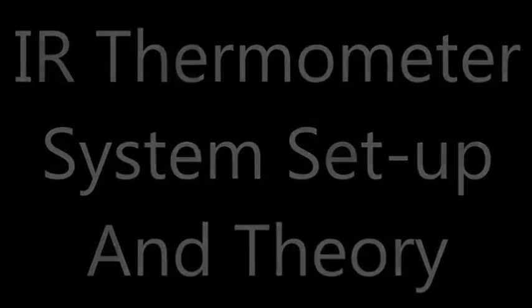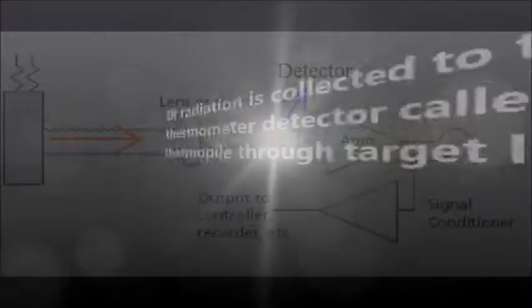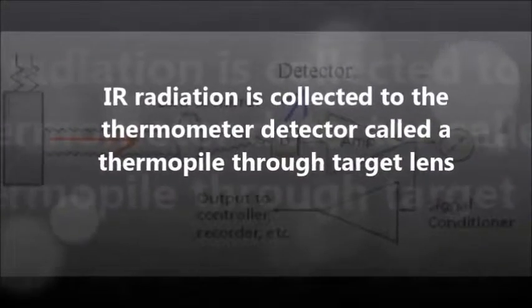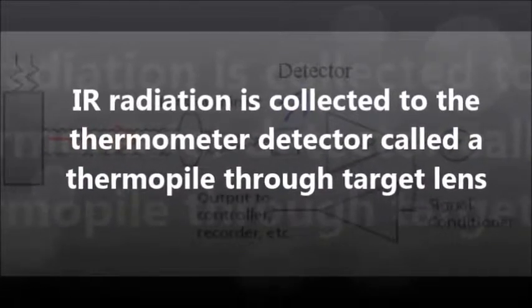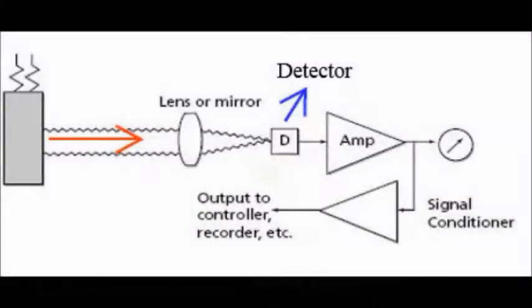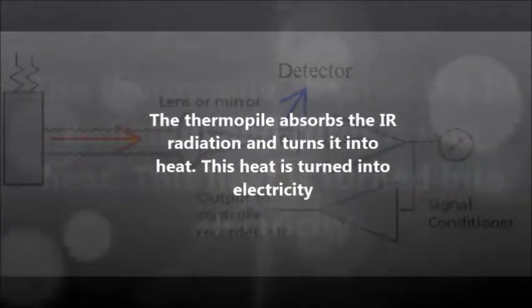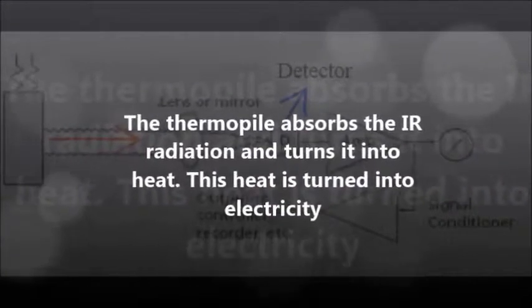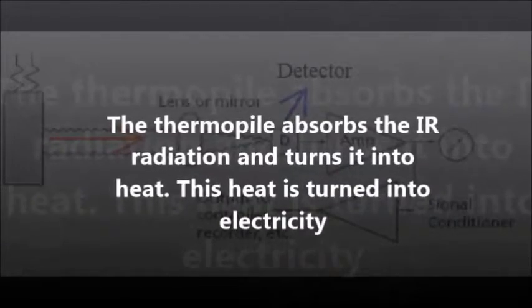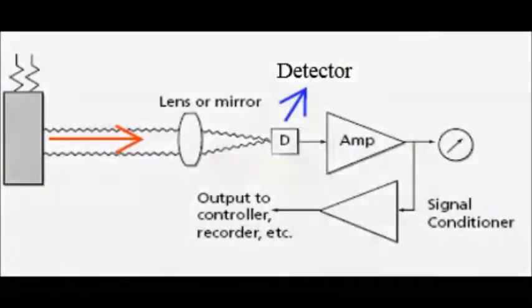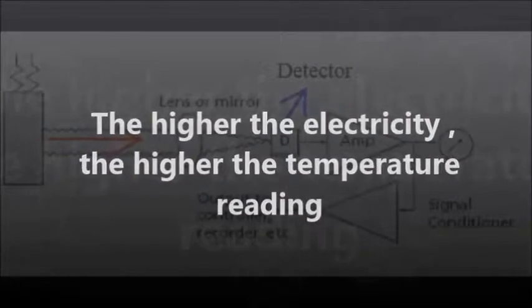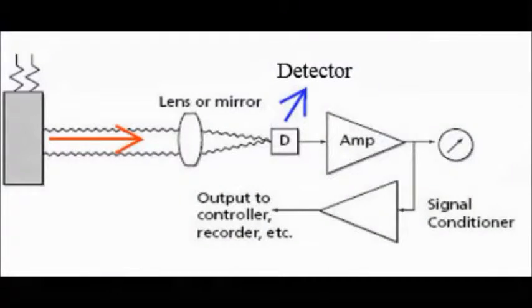IR thermometer system setup and theory. IR radiation is collected by the thermometer detector, called a thermopile, through a target lens. The thermopile absorbs the IR radiation and turns it into heat. This heat is turned into electricity. The higher the electricity, the higher the temperature reading.